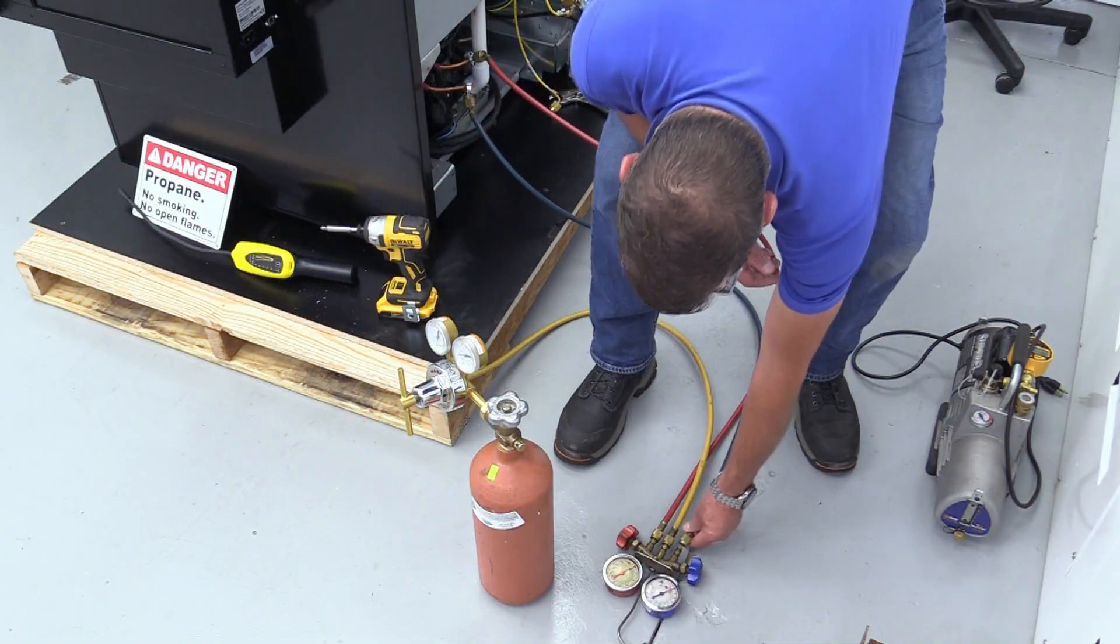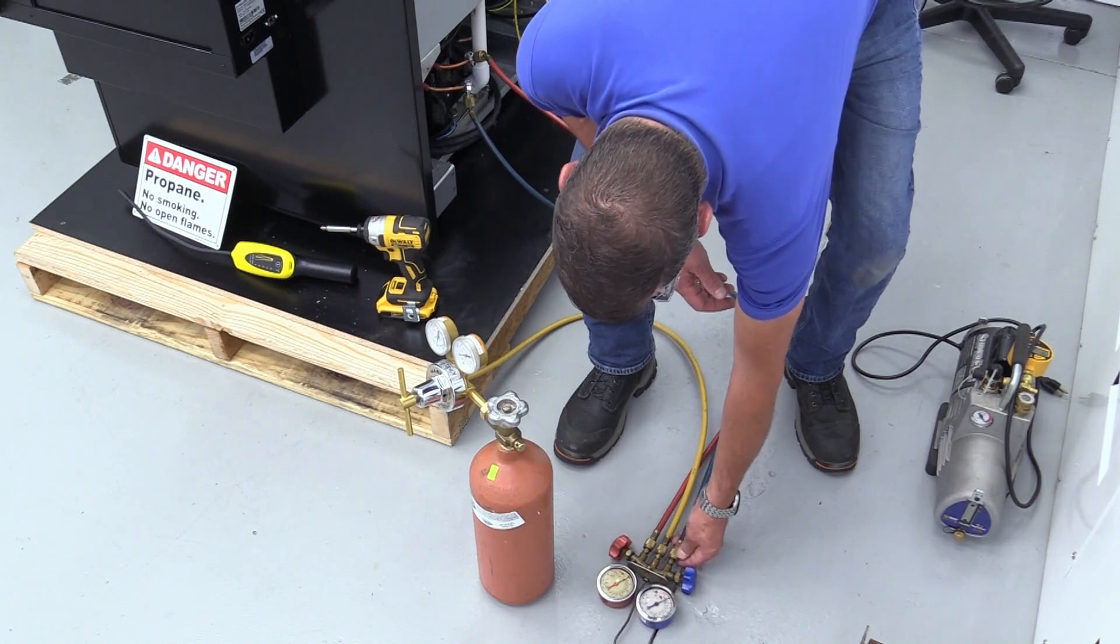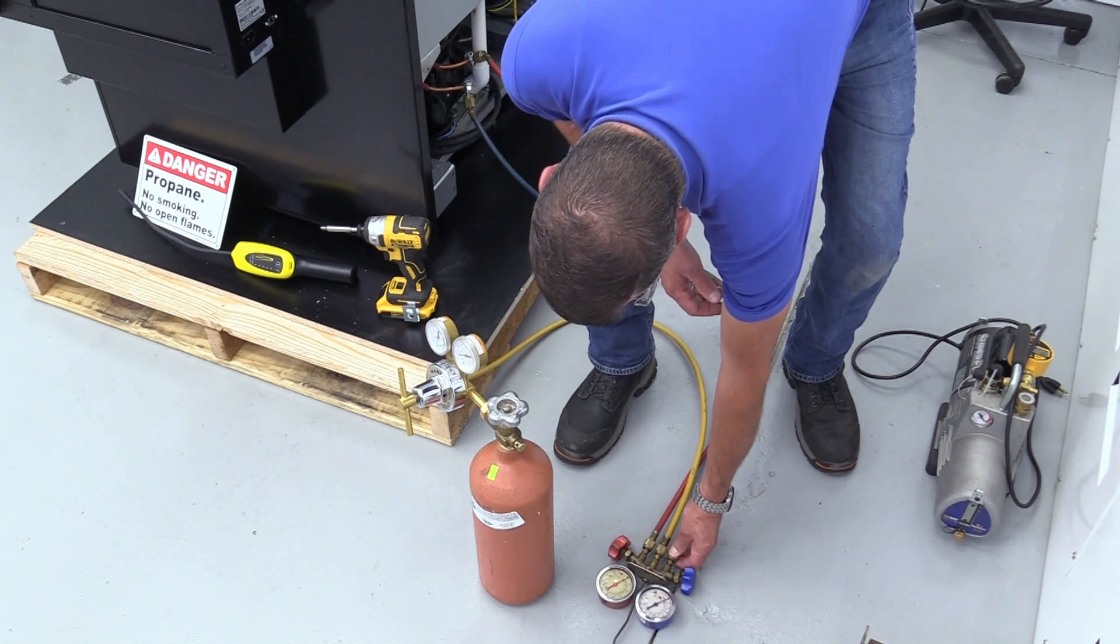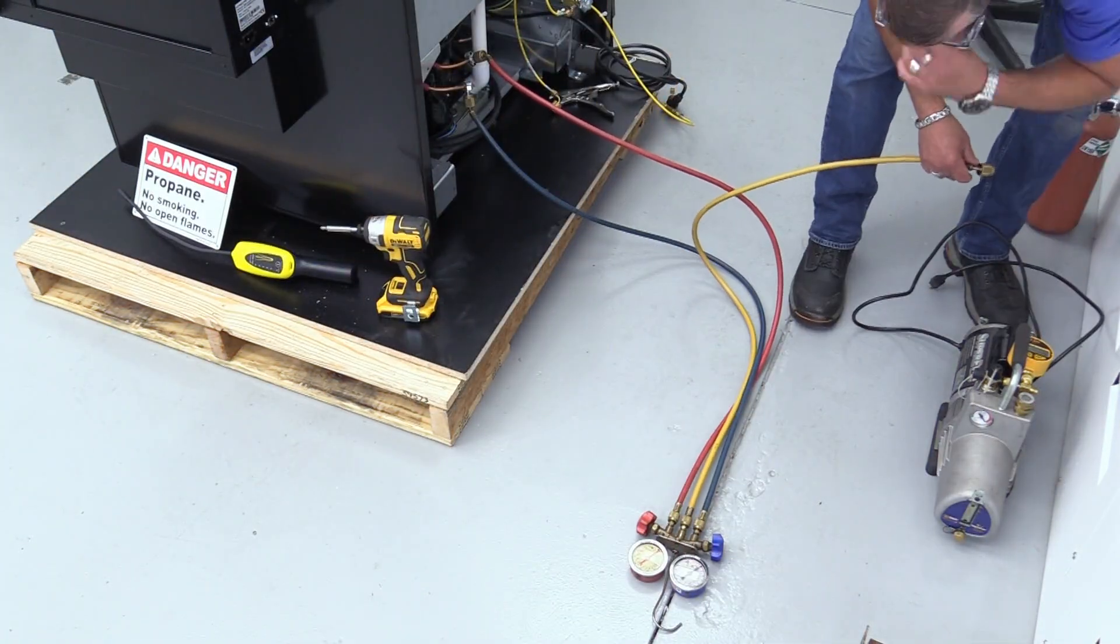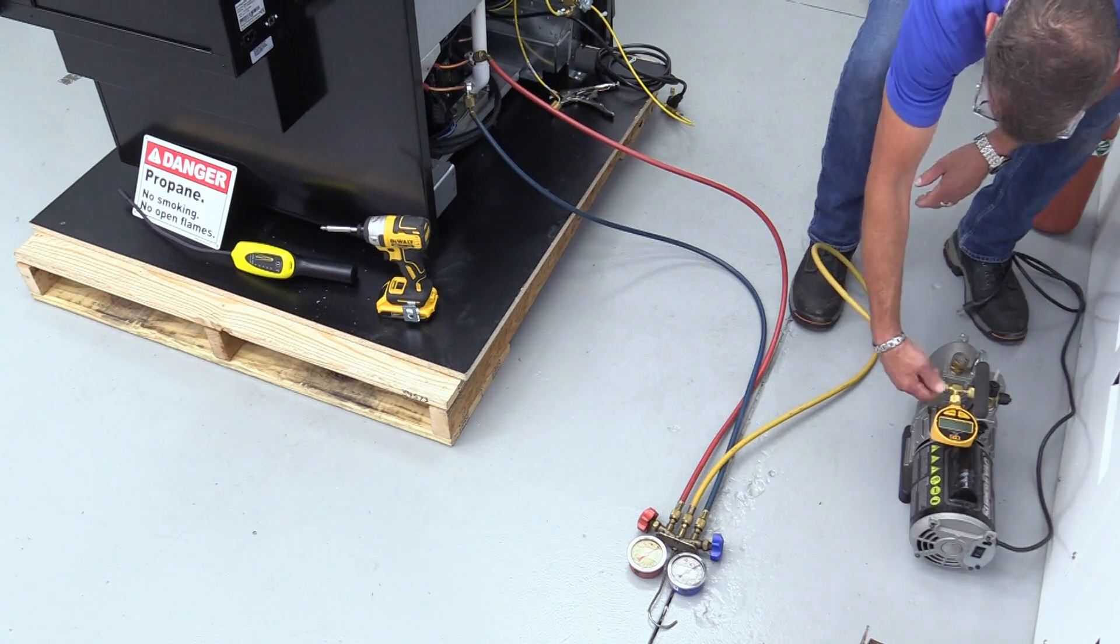Pressurize the system with nitrogen at 200 PSIG and check for leaks. Vacuum the system to below 500 microns and ensure the vacuum sustains for 10 minutes.